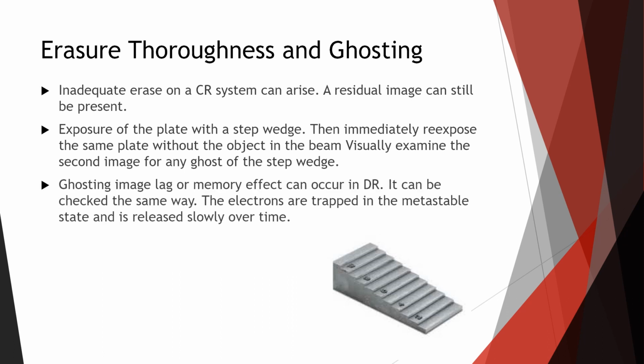In DR, ghosting, image lag, or memory effect is what it can be called, can occur. It can be checked the same way. So we can do the same exact process with this, re-expose it, see if there's still something there. The electrons are trapped in a metastable state and are released slowly over time.